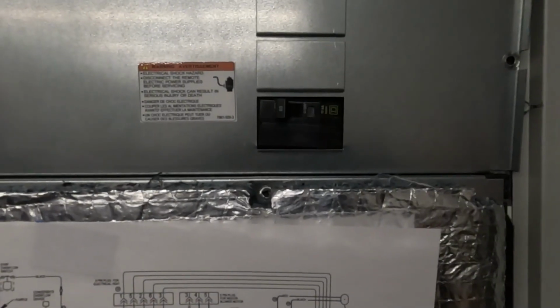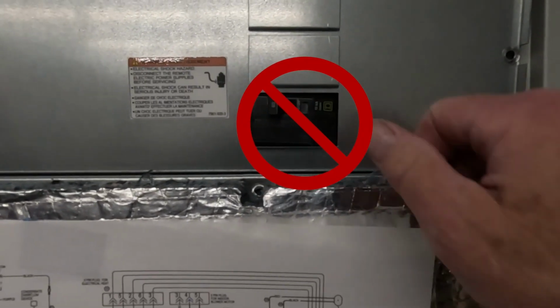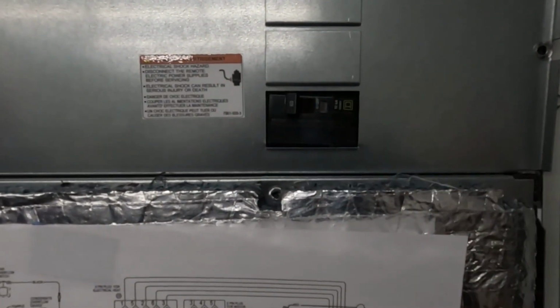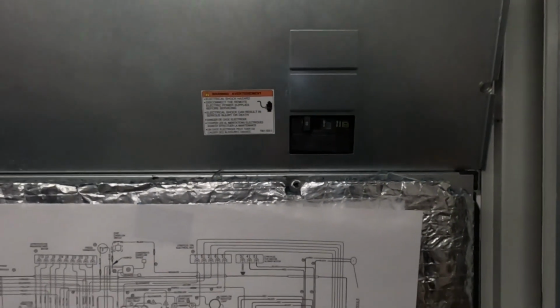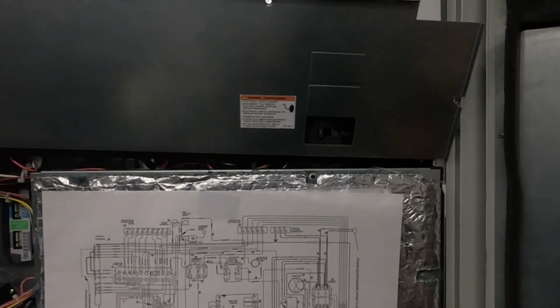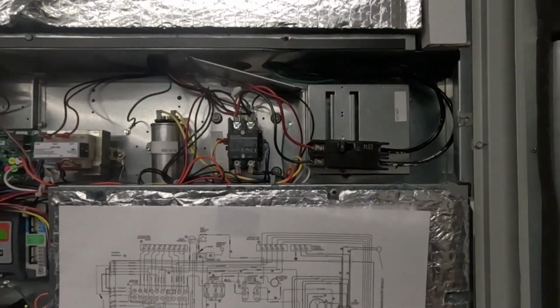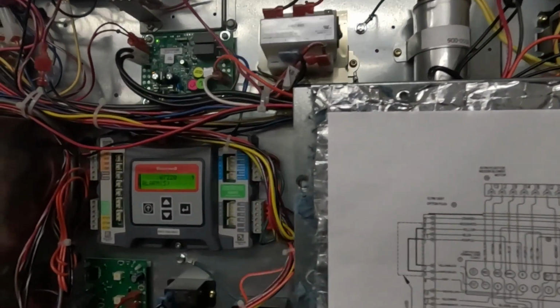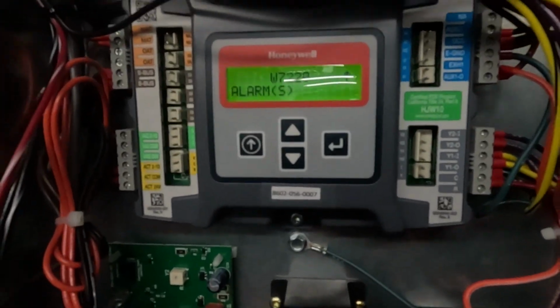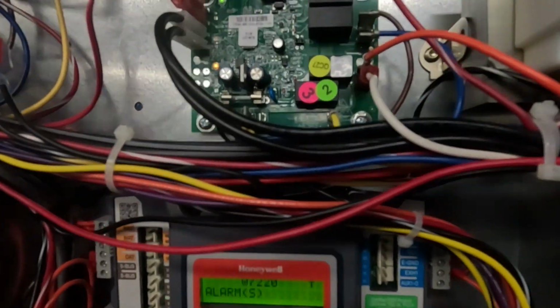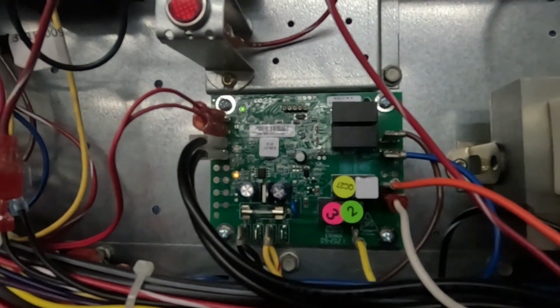Take a photo of the unit data tag with the model and serial number should you want to contact tech service. Often we are taught to turn off the circuit breaker to work on a unit. You're an experienced service tech. I'm going to suggest you do not turn off the circuit breaker just yet. If you do, the unit will clear all memory and reset any info or alarms that might be available. You may need to turn off the circuit breaker at some point, but first collect any available information.